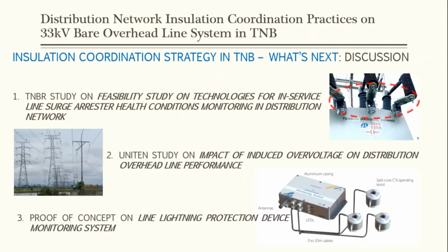But the current existing bare medium voltage overhead lines still need to be taken care of, right? So we still have a TNBR study on feasibility study and technologies for in-service line surge arrester health conditions monitoring in distribution network. So the line surge arrester would be the main protective device for ensuring that we minimize or mitigate the lightning interruptions for TNB medium voltage overhead lines. So we need to ensure that the surge arresters are always in a good condition.